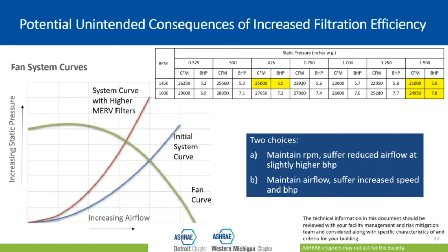The other choice is that the fan can deliver the right amount of air to the space. But when we do that, we can see that our horsepower goes up. This graph here, which is just a cutout, shows that as the static pressure goes up, the airflow goes down, so we're losing that. But we're also seeing our brake horsepower going up, right? And as we continue to do that, the airflow just continues to drop and brake horsepower continues to rise, right?